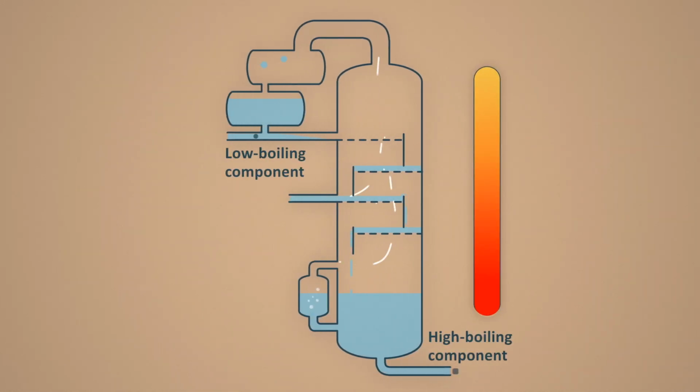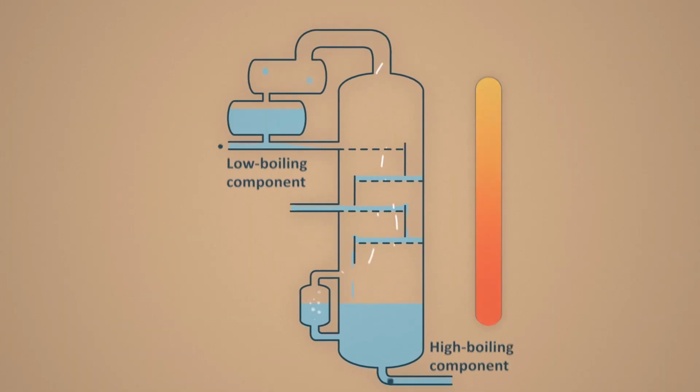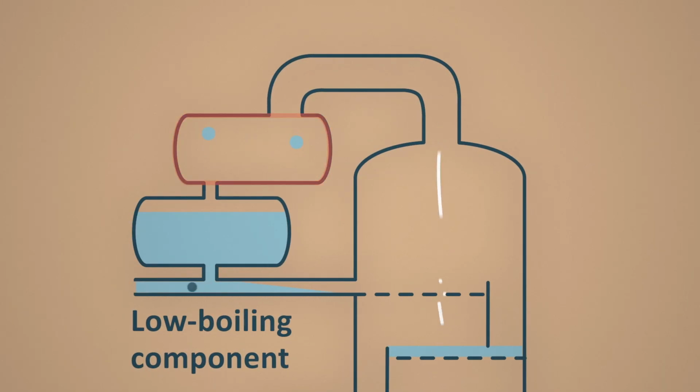Therefore, liquid spraying called refluxing is also required. For this purpose, the reflux exchanger condenses the vapor at the top of the tower. The condensed liquid accumulates in the reflux tank and enters the top tray as a reflux. The required temperature mode is obtained in the fractionator by adjusting the flow rate of steam spraying and refluxing. That ensures that the final product gets the commercial quality.